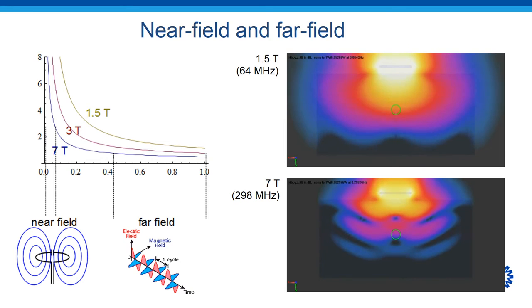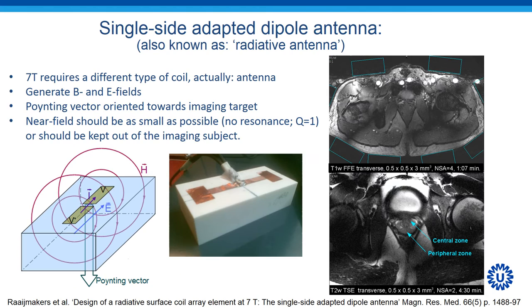Whereas at 7 Tesla, the region of interest is very much in a wave-like regime, which is approaching the far field. This shows that for prostate imaging at 7 Tesla, we need a different type of coil, or actually, we need an antenna.